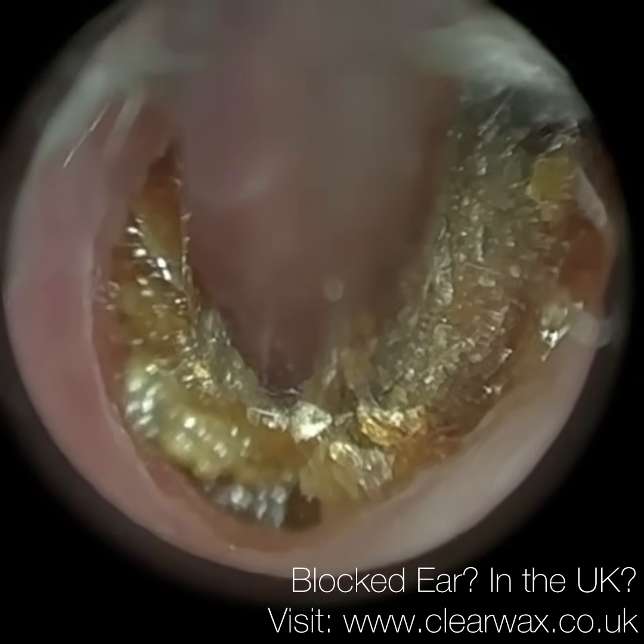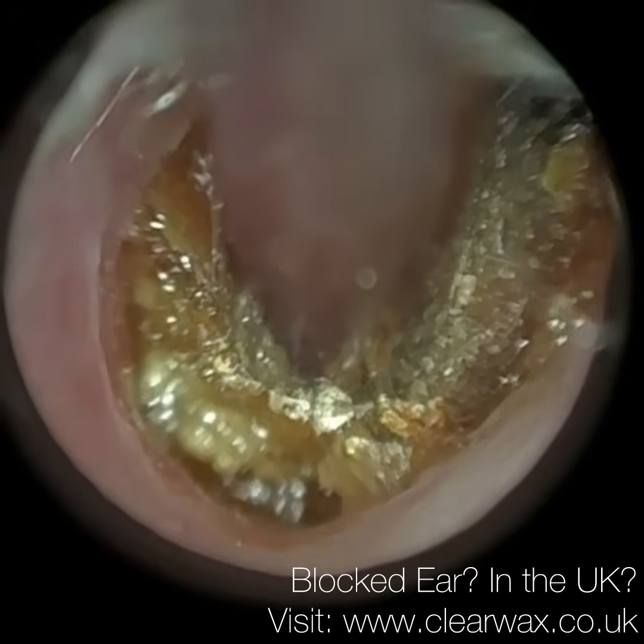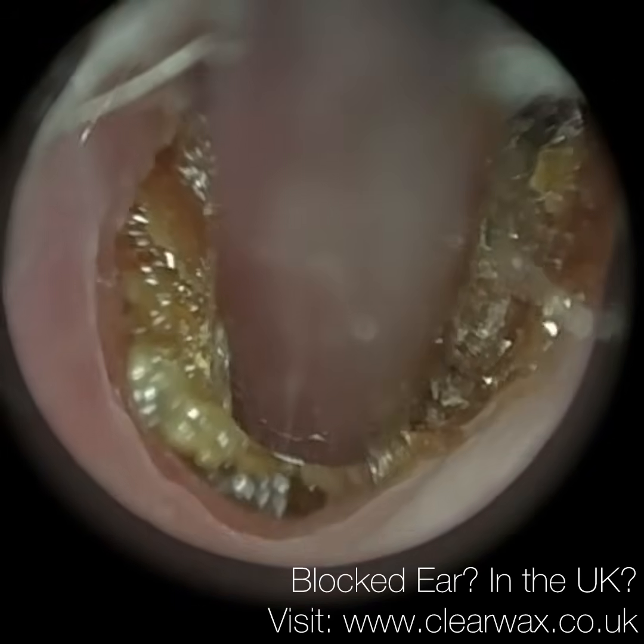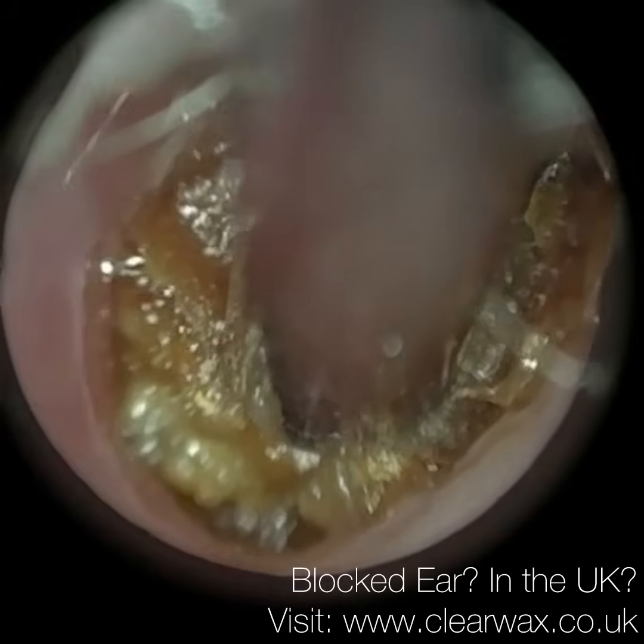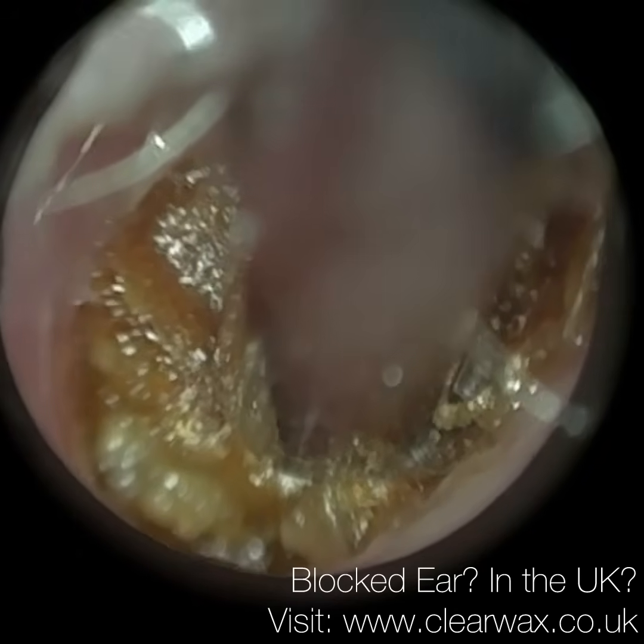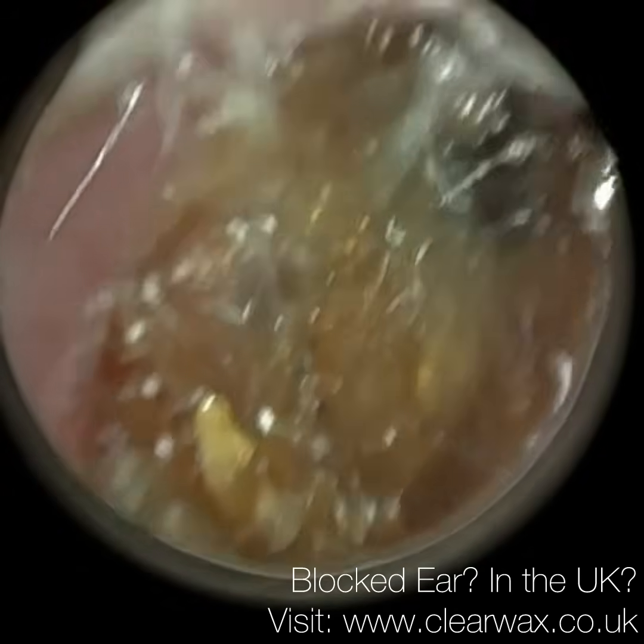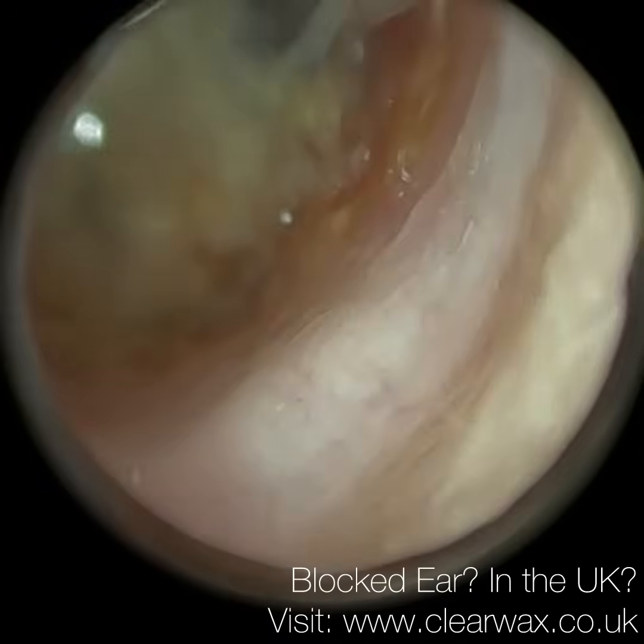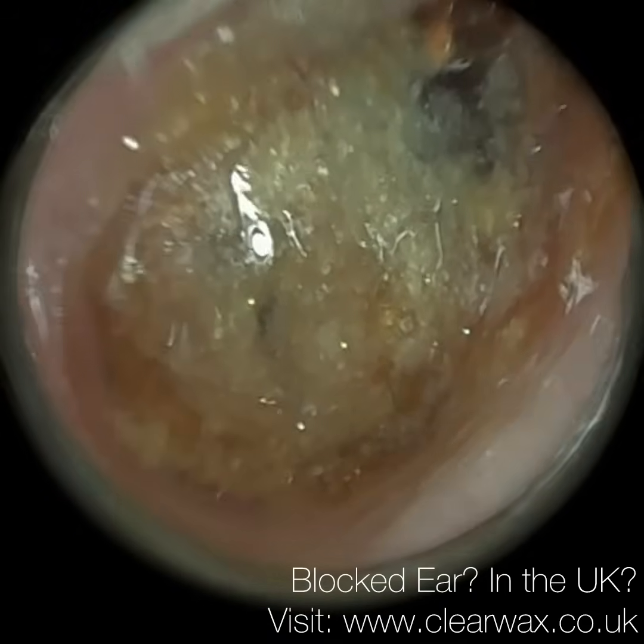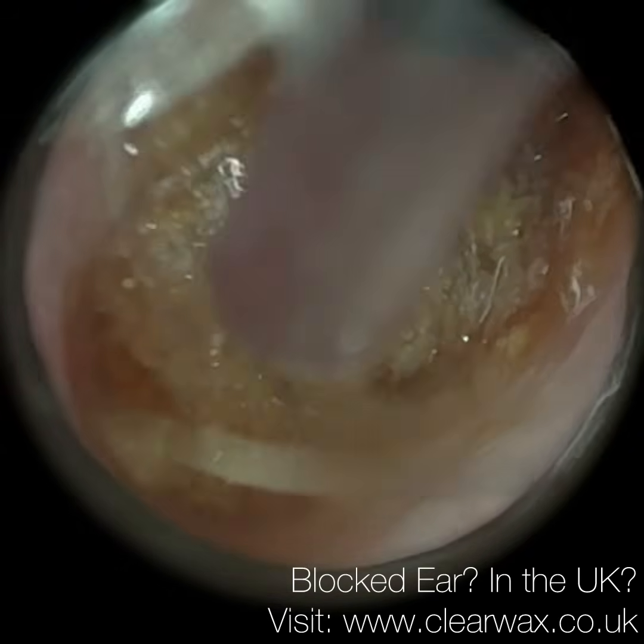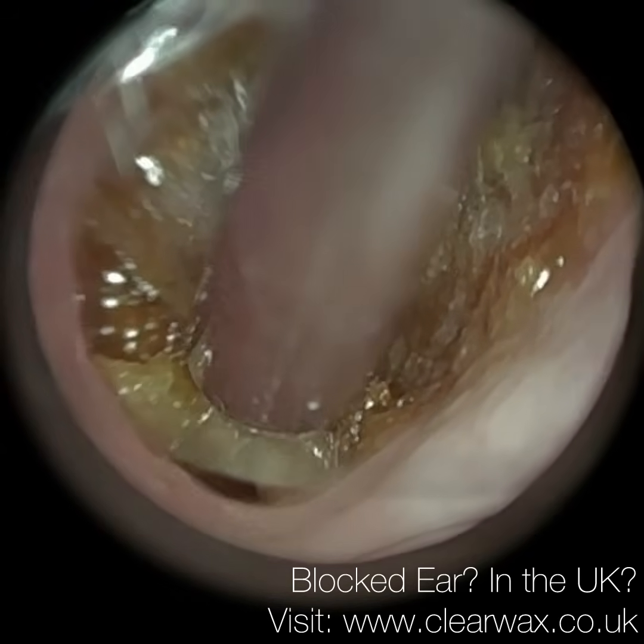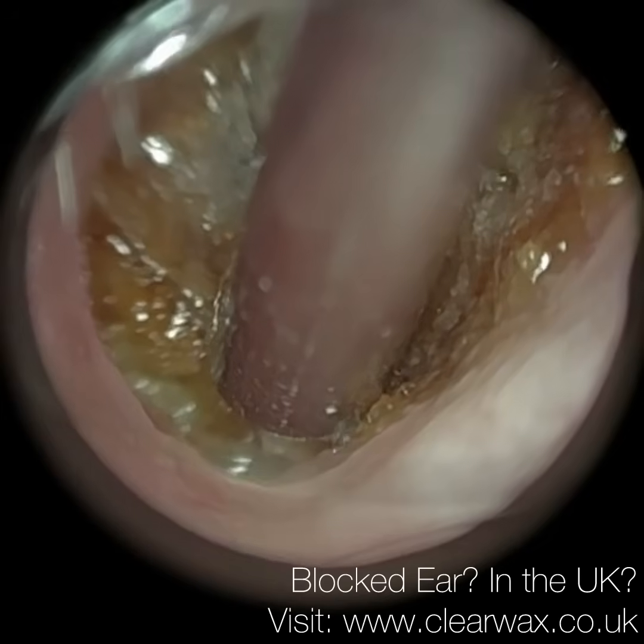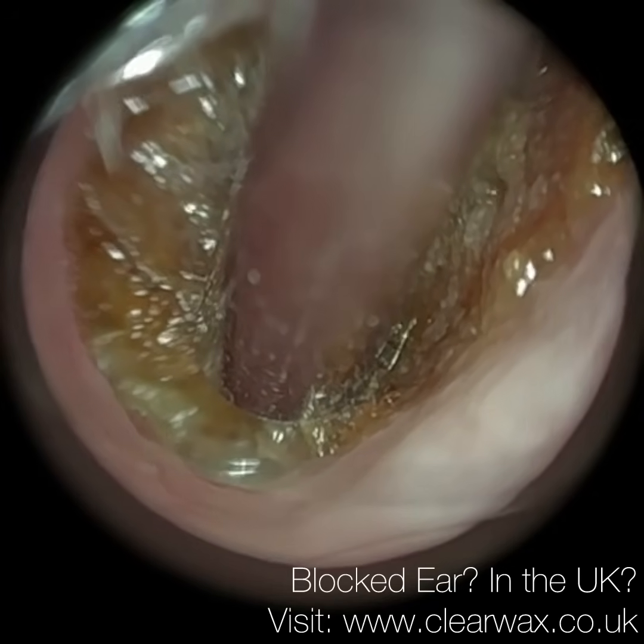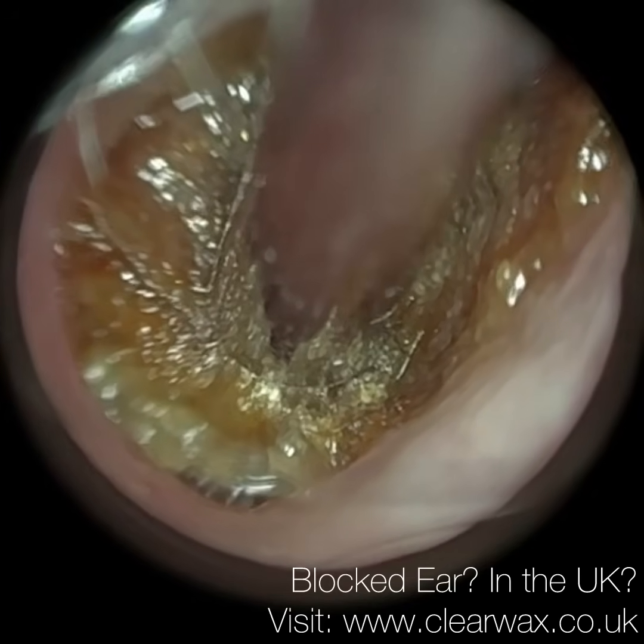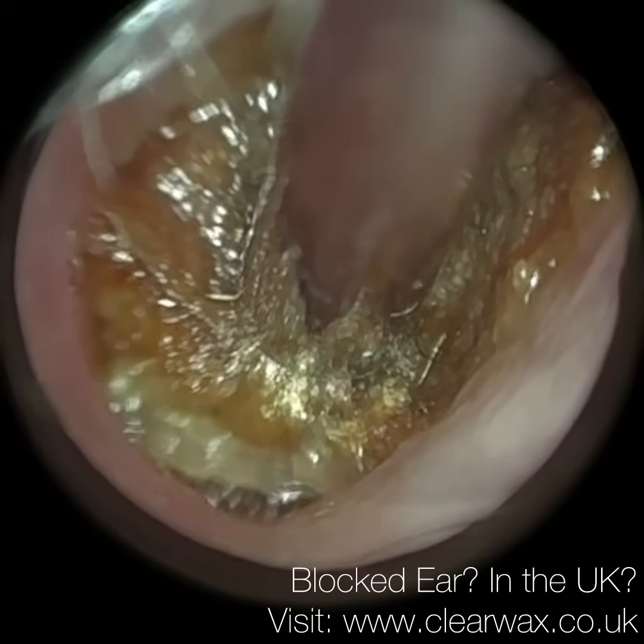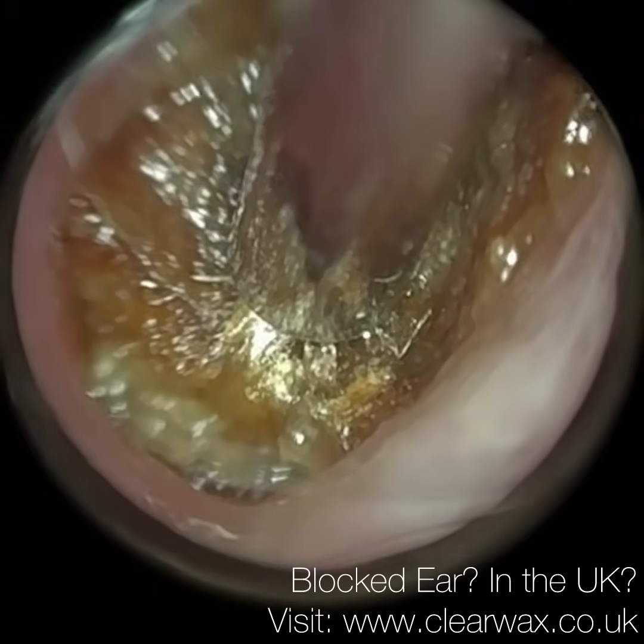So with the 14 gauge, although it has more suction power, when you've got a flat surface like this, you're more likely to get a less airtight seal. Essentially, the tip of the suction probe is not fully embedded all the way around on the earwax, which means there's a leakage. When you get leakage, some external air is suctioned into the suction tip, which decreases the overall suction power of removing the wax.